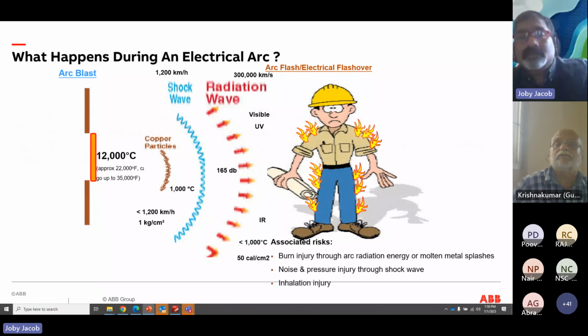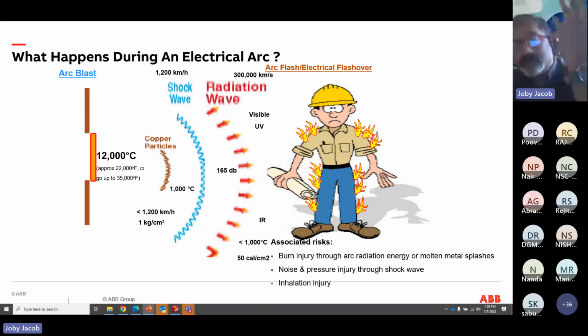So what happens during an arc? An arc flash blast occurs at around 12,000 degrees Celsius. It emits molten copper particles, which normally travel around 1,200 kilometers per hour. It includes a shock wave, so if you are in front without any ear protection, you could be temporarily or permanently deaf. The radiation, the heat wave which ignites you, travels at 300,000 kilometers per second, the speed of light. It is also related to burn injury through arc radiation, noise, and pressure injury.